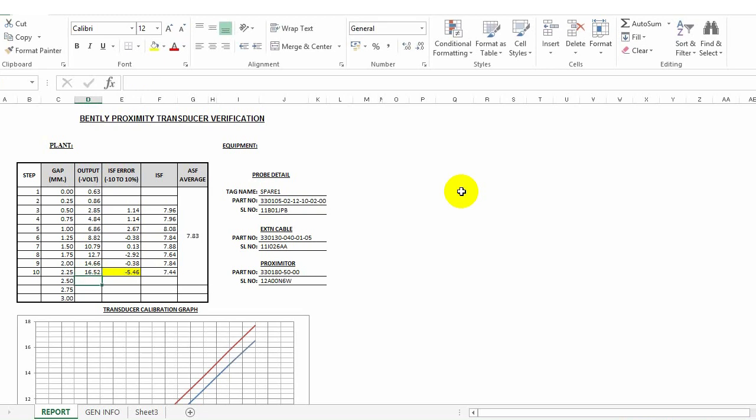When all the steps are complete, if the ISF and ASF are within specified limits, the proximity transducer system is verified OK.